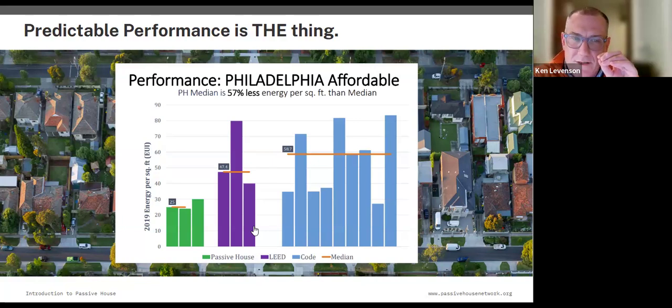So we did install 3 tons, but that's a variability of 1.5 tons. And it's effectively a 75% reduction, at least in the sizing of the equipment. And I'm very happy. It was a little nerve-wracking, but it's that predictability, the calculation, the predictable performance that allowed us to do that. And the owners, it performed well. The owners were very happy.